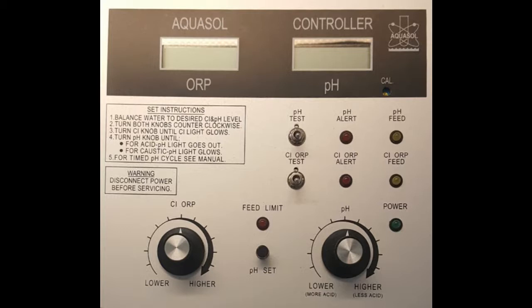Okay, so looking at a couple of these features, going a little more in depth. pH set is not going to do anything unless timed monitoring is selected on, what is that, dip switch 2? 1 and 2 in conjunction. So for the water management program, those are always going to be in the off position. So the pH set button would not do anything if those are off, correct? Correct.